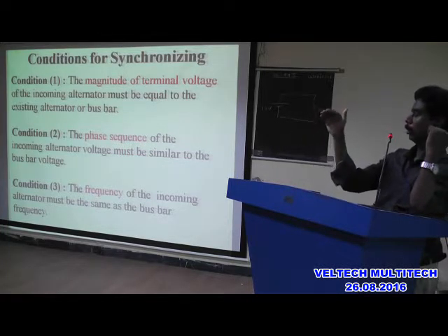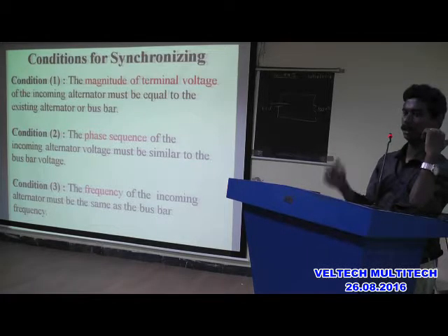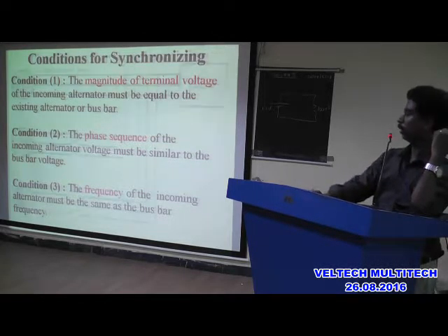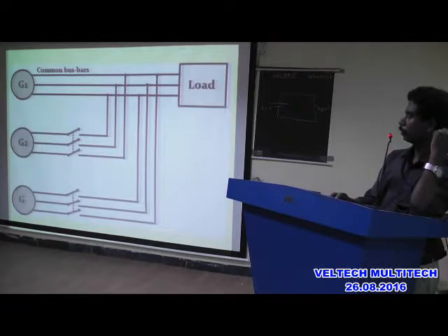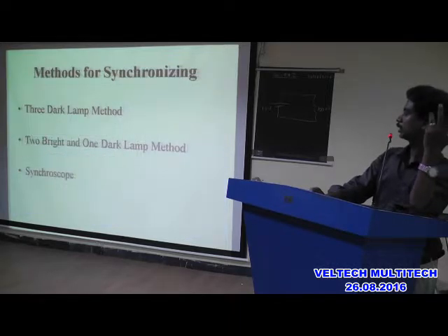You have to follow the same order. First you have to satisfy the voltage, next phase sequence, next frequency. You should not change the order. Once you satisfy these conditions, you can add n number of alternators to the existing bus bar or existing alternator.